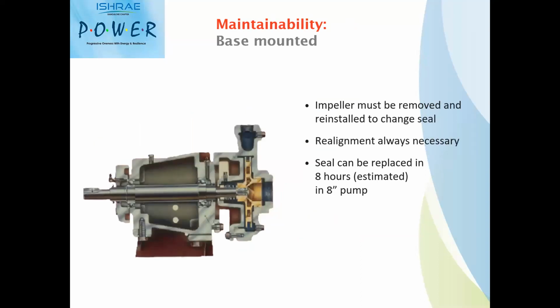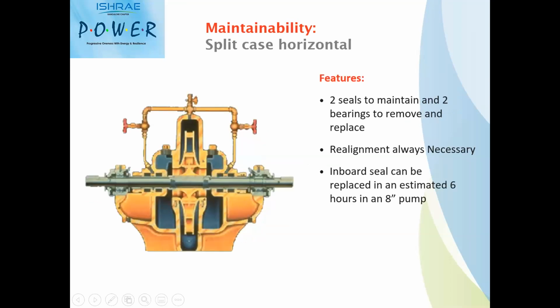And in terms of maintenance, an end suction pump has a typical bearing assembly with two bearings, inward and outward. In addition to that, you will have two separate motor bearings also. Since these pumps are mounted on a base plate, they require realignment very frequently. In general, once in 3 months or once in 4 months, we need an alignment check, since alignment goes off. If misalignment happens, it tends to damage your bearings as well as mechanical seals, since it is a cantilever design. When it comes to horizontal split case pumps, as I mentioned, there are 2 mechanical seals and 2 bearings to be maintained. Again, it is a base mounted design pump, and it definitely requires alignment frequently.